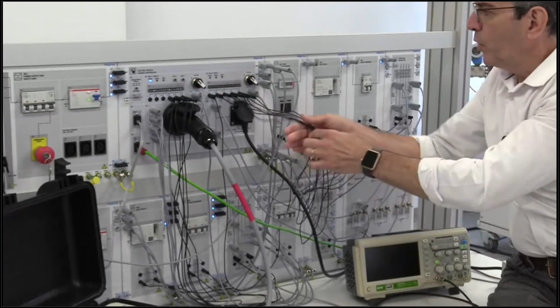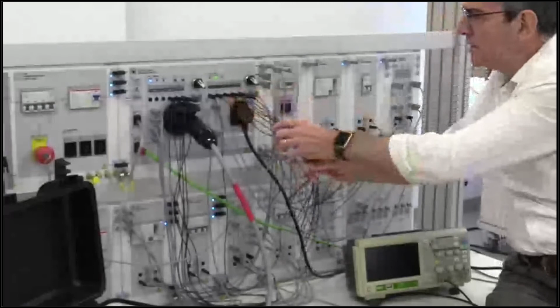Then, what about these small black cables here? They are the sensing circuit I mentioned. Leaving from terminals 15, 16, and 17, I am connected to the various normally open and normally closed contacts on each device to know their current state.